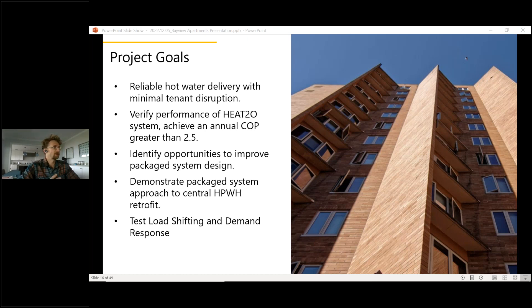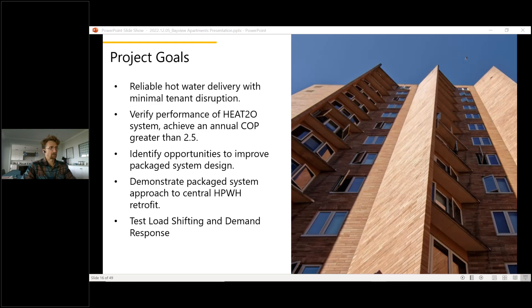Project goals included: keeping hot water running to tenants, achieving a target COP of 2.5, identifying design improvement opportunities through measurement and verification, demonstrating a pre-built package system approach for easier on-site installation, and testing load shifting and demand response.